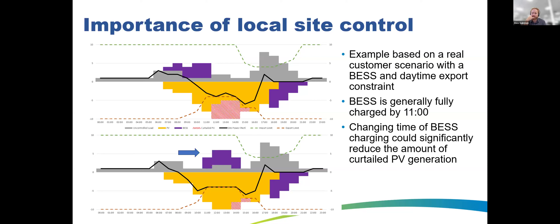Will proposed regulatory resets consider oversized transformers to enable export options for residential PV? If a transformer is overloaded with PV or load it can be triggered for augmentation, though that process is slow and costly. The whole point of operating envelopes is to reduce that need for augmentation. If customers are only curtailed one day per year, it makes more sense to reduce PV generation on that one day rather than spend significant dollars on transformer augmentation. But if customers are being curtailed every single day, then upgrading the network clearly makes more sense. It depends on the severity of the constraint.